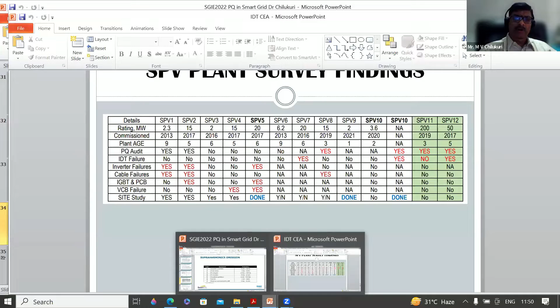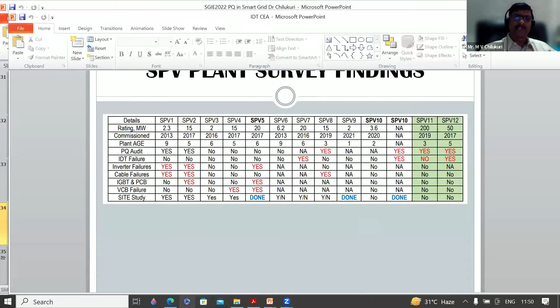Yeah, quickly. So here what I would like to say is, when we investigated the issue at 10 to 12 plants, we found not only inverter duty transformer failures, but also VCB failures and IGBT failures in the inverter. Many things are happening, and there is no provision for proper PQ monitoring. So our suggestion is that power quality should be monitored not only at the PCC, but inside the plant. Most of the failures are happening due to transients, so transient measurement is very, very important, which I would like to highlight in this discussion. Thank you.